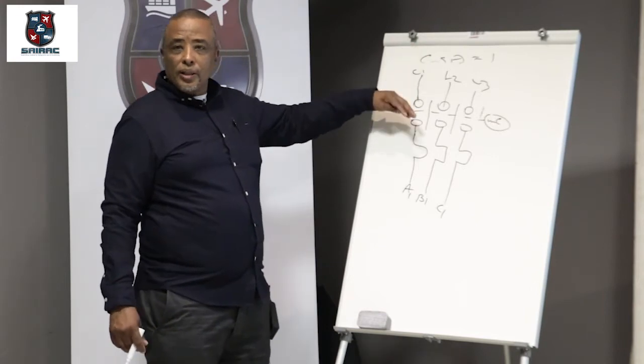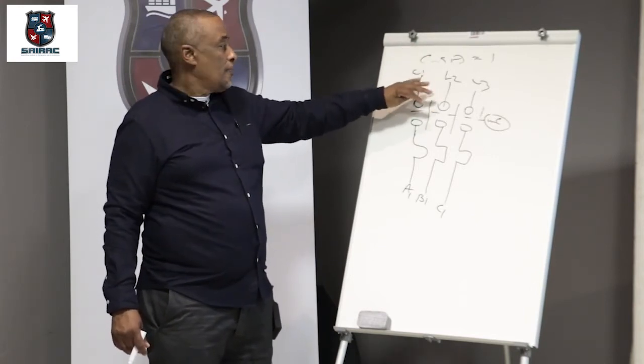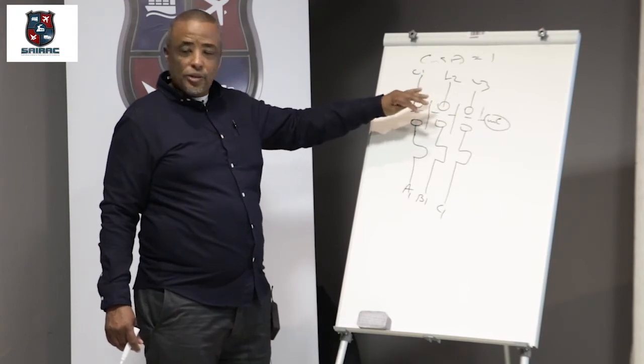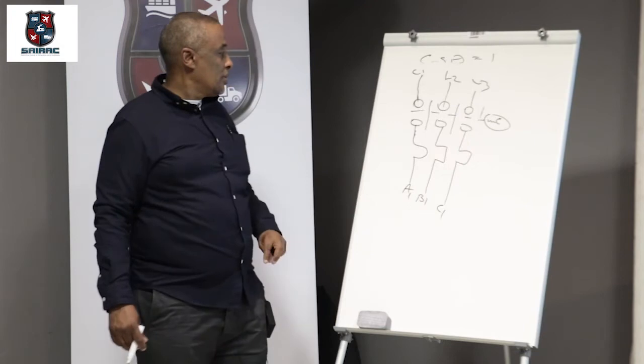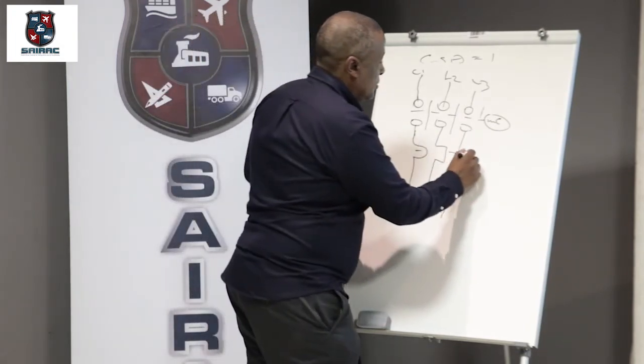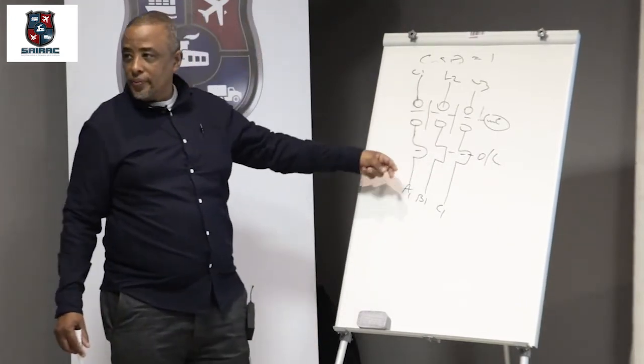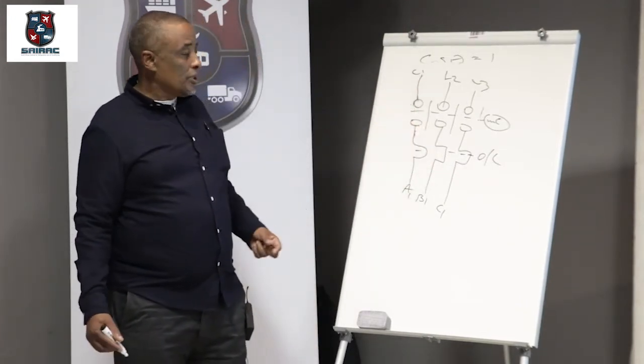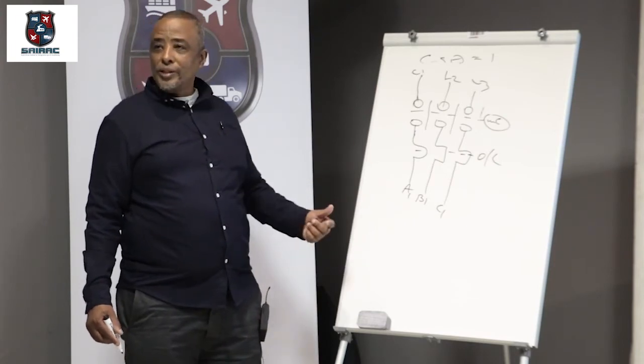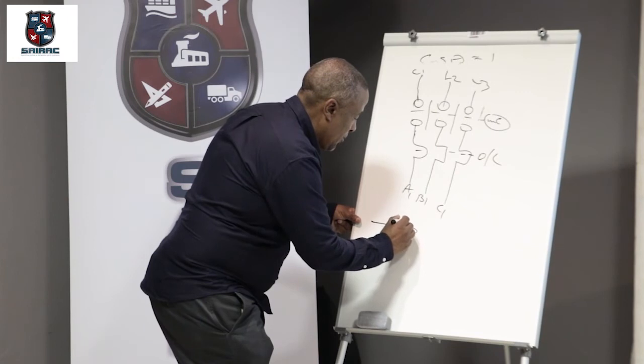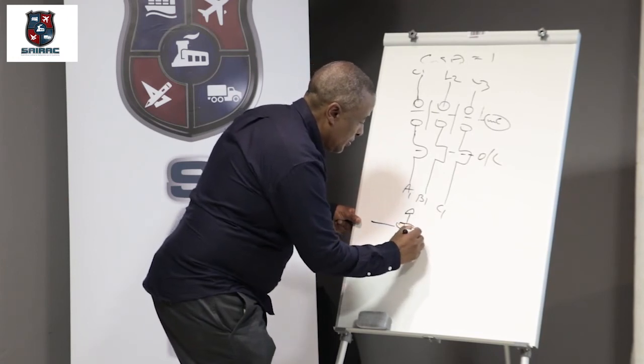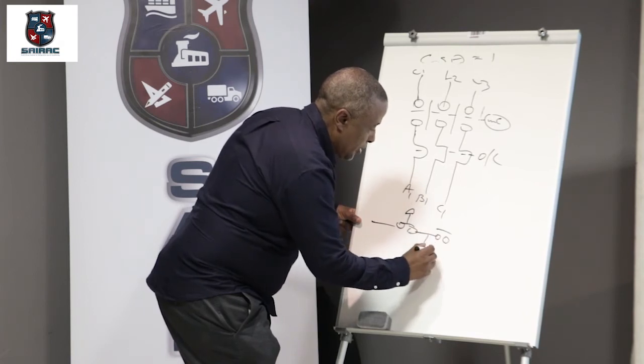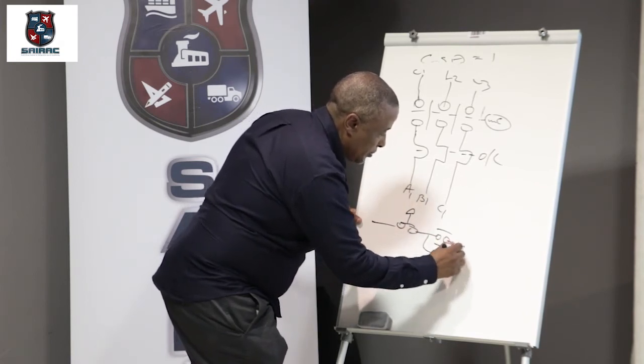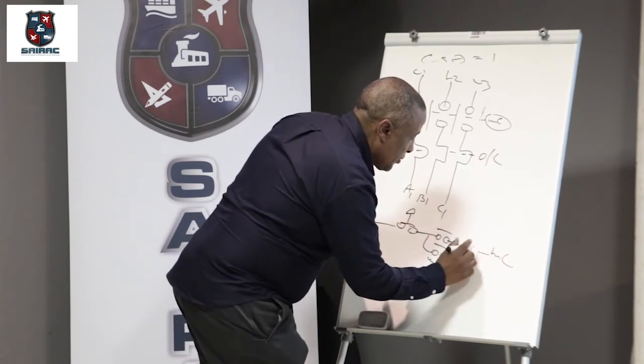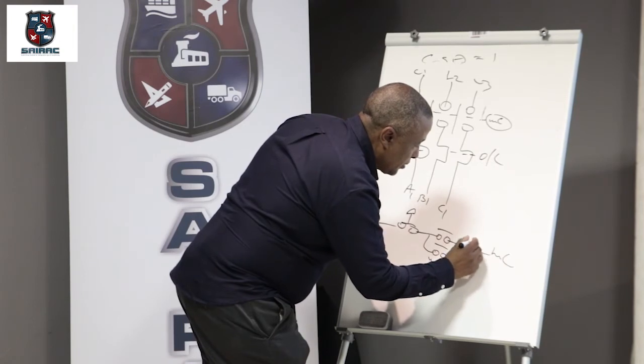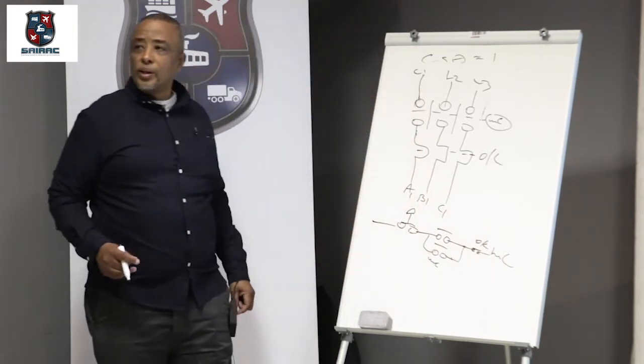This is basically the power circuit for a direct online starter. It's basically just a contactor with a coil and your overloads. You all have seen that in the field. It's a direct online starter. The control circuit will consist of a start button, first of all with a stop button, start with a retainer, maybe you can put the overload there. Happy with that? Familiar with that?